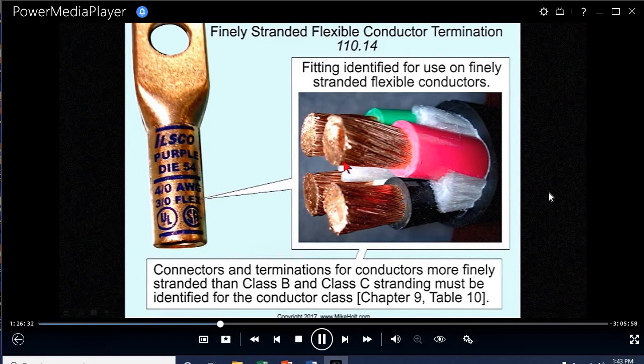So you can see this is, I don't know what this is, but this is probably what they call diesel locomotive cable, DLO. A diesel locomotive cable cannot be used because that's not a code wiring method, unless that wiring method has a dual rating. And that wiring method is probably going to be rated RHH/RHW, DLO, diesel locomotive cable. Yes?